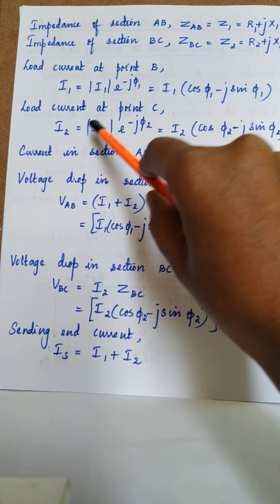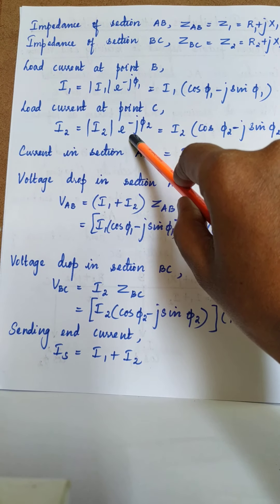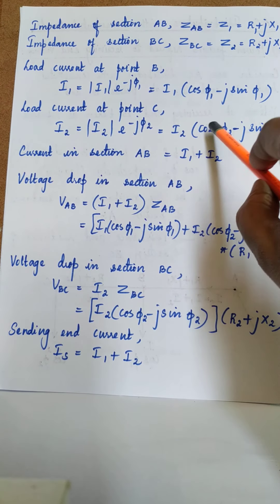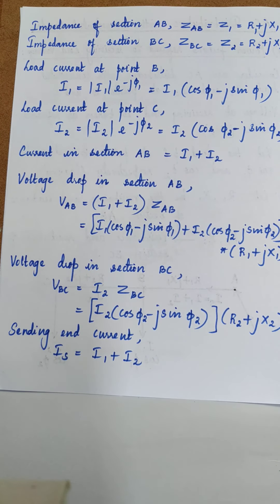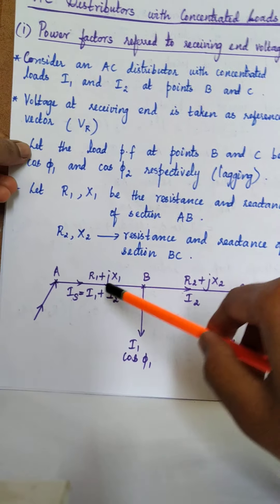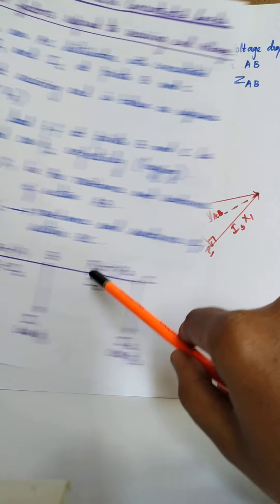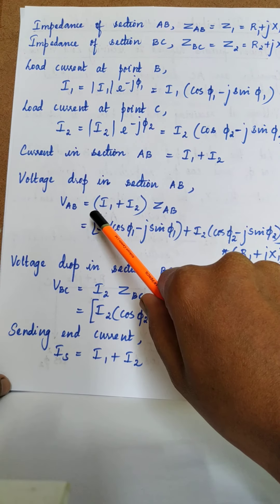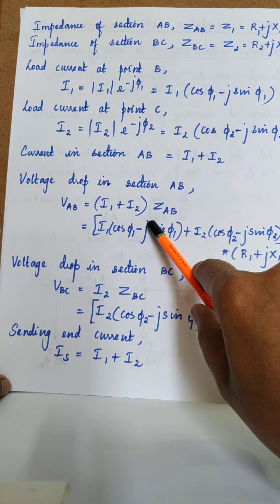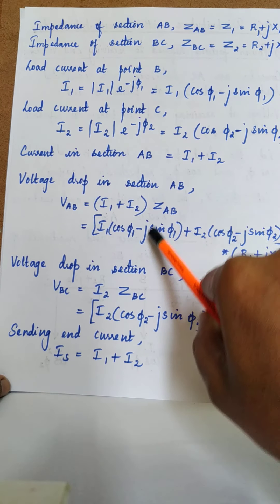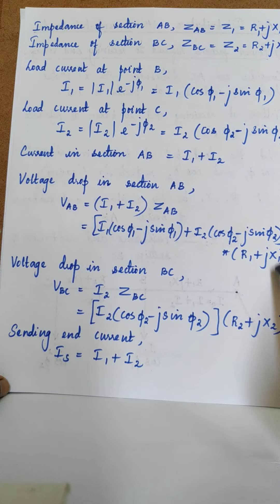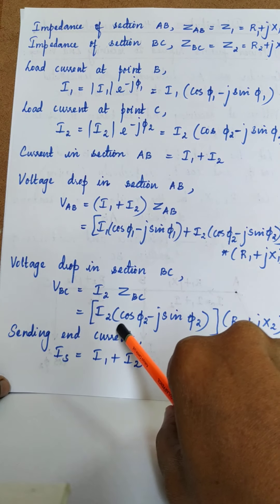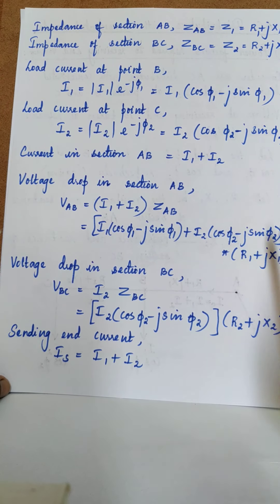Similarly, the load current at point C is I2 equal to magnitude of I2 times e to the power minus J phi 2 — again minus because of lagging power factor cos phi 2. Expanding, we get I2 times (cos phi 2 minus J sin phi 2). The current in section AB is I1 plus I2, which is the sending end current. The voltage drop in section AB is VAB equal to (I1 plus I2) into ZAB, substituting I1 and I2 and ZAB equal to R1 plus JX1. The voltage drop in section BC is VBC equal to I2 into ZBC.